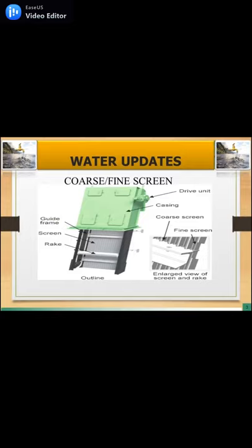Once the wastewater reaches the plant, the first stage is the screening process. The incoming wastewater passes through screening equipment where objects such as rags, wood fragments, plastics, and grease are removed. The material removed is washed, pressed, and disposed of in a landfill. The screened wastewater is then pumped to the next step, grit removal.